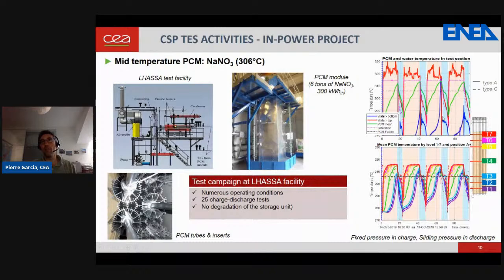Here you have the steam and water temperature at the top and bottom, in blue and red. You can also see the saturation temperature in pink, and the PCM mean temperature in the storage tank in green. Below, we can see the PCM temperature at different levels of the storage system during charge and discharge. We observe very controllable, well-controlled and repeatable conditions, with fixed pressure in charge and sliding pressure in discharge.